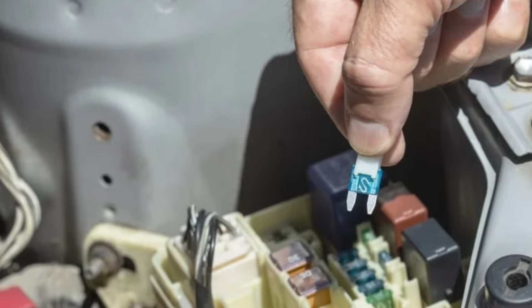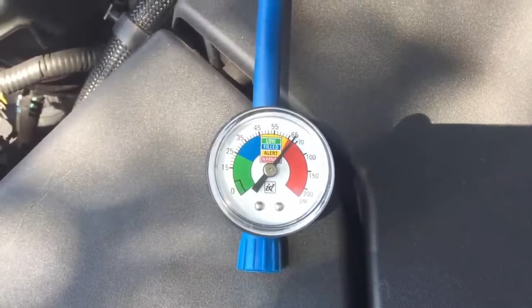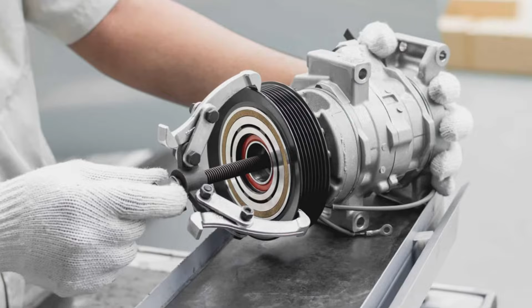Wrong refrigerant level. For optimal operation, the air conditioning system requires the appropriate amount of refrigerant. The issue could be brought on by either an excessive or insufficient amount of refrigerant. The modern system uses an AC pressure switch lockout mechanism to safeguard the valuable components in case the refrigerant level isn't correct. The AC compressor clutch will not engage and power will be cut off if the pressure in the system is too high or too low on the high pressure or low pressure sides.